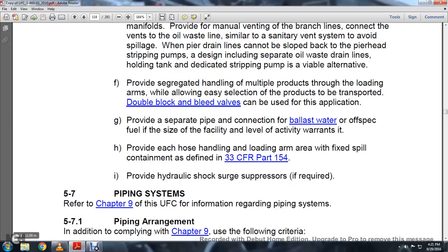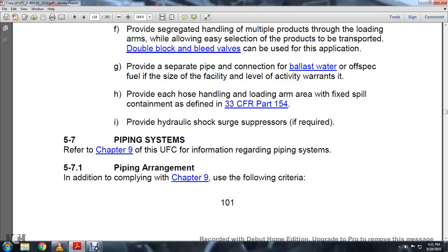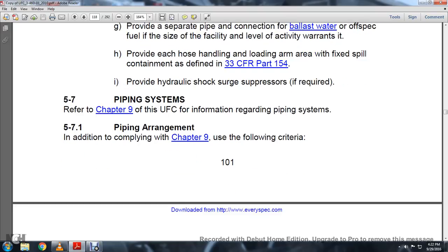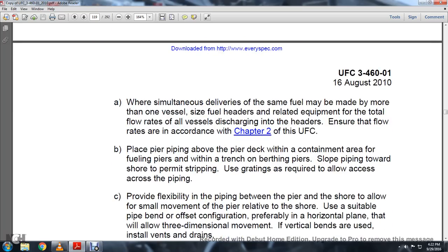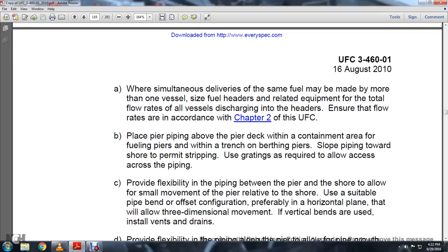5.7 Piping system. Refer to Chapter 9 of the UFC for information regarding piping systems. 5.7.1 Piping arrangement. In addition to complying with Chapter 9, use the following criteria. Where simultaneous delivery of the same fuel may be made to more than one vessel, size the fuel headers for the total flow rates of all vessels discharging into the headers, which will ensure that the flow rate is in accordance with Chapter 2 of the UFC.